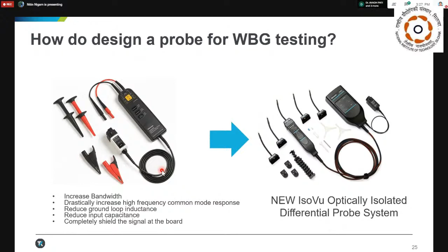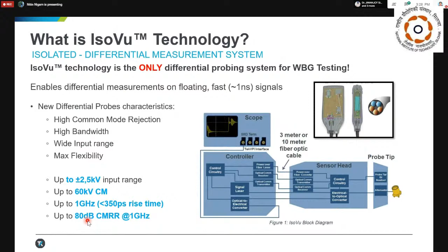This is one of the proprietary technologies that really needs to be understood, working at a 2.5 kV input range with a 60 kilovolt common mode rejection ratio. The frequency range goes up to 1 gigahertz, and the CMR ratio at 1 gigahertz is 80 dB. Compare this to a normal differential probe, which was limited to 100 megahertz with a common mode ratio of around 25 dB. Now we're talking 80 dB at 1 gigahertz, so we've drastically increased the CMR values with respect to frequency range. High common mode rejection, high bandwidth, and wide input flexibility give you the maximum accurate measurement results.